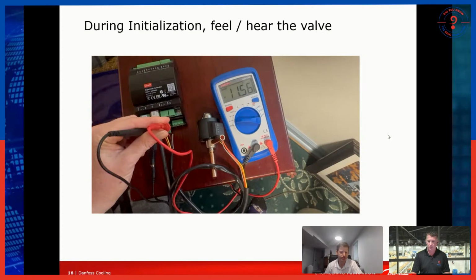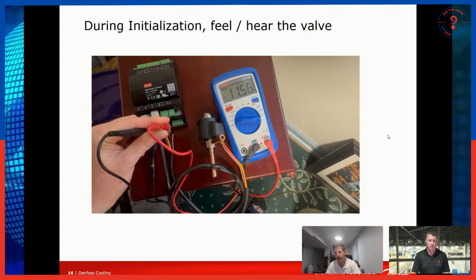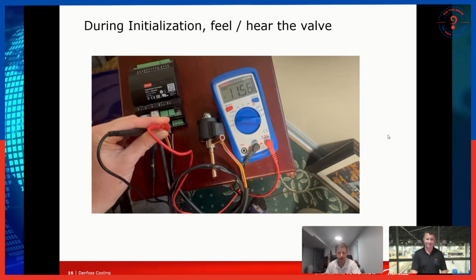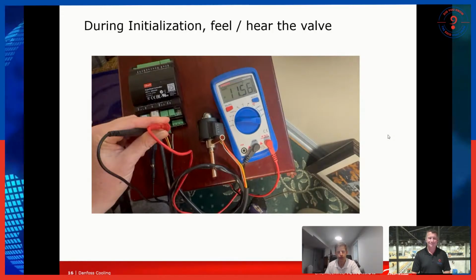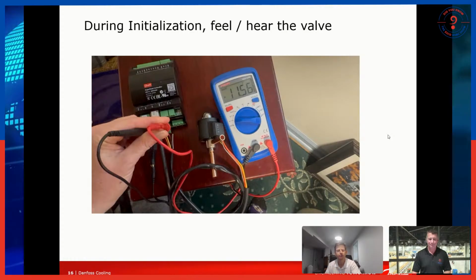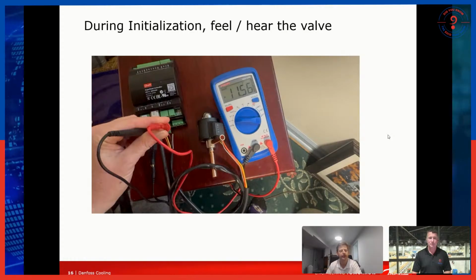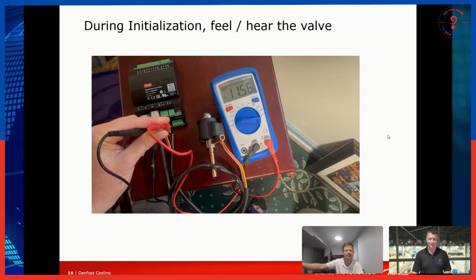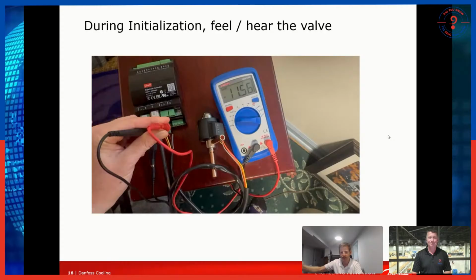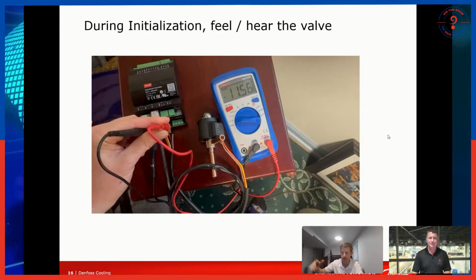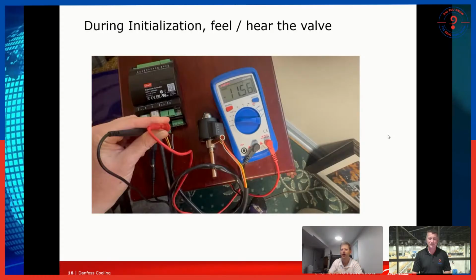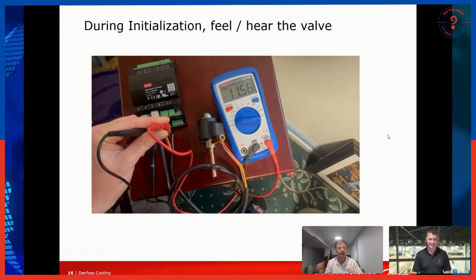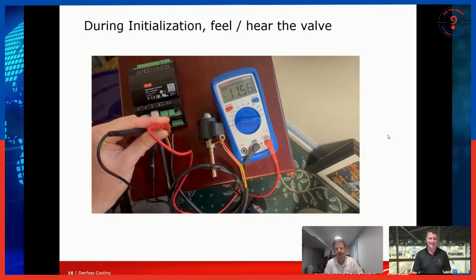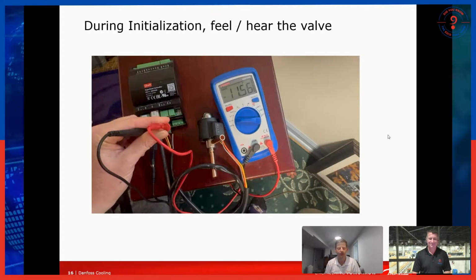Yeah, and temperature sensors operate entirely on resistance, so you can ohm them out and see what you're getting. You might be able to use that to help you. Probably the main thing you're going to see there is whether you get resistance or you don't. If you don't, it lets you know the wire's cut or something. And that's probably as far as you'll get with that. But even there, you could track down, okay, this is a 2K sensor, meaning it's meant to be at 2,000 ohms at room temperature, I believe. Don't quote me on that part, but you can track down a chart if you really want to troubleshoot your temperature sensor. Like, is it reading the right ohms for what the temperature is?